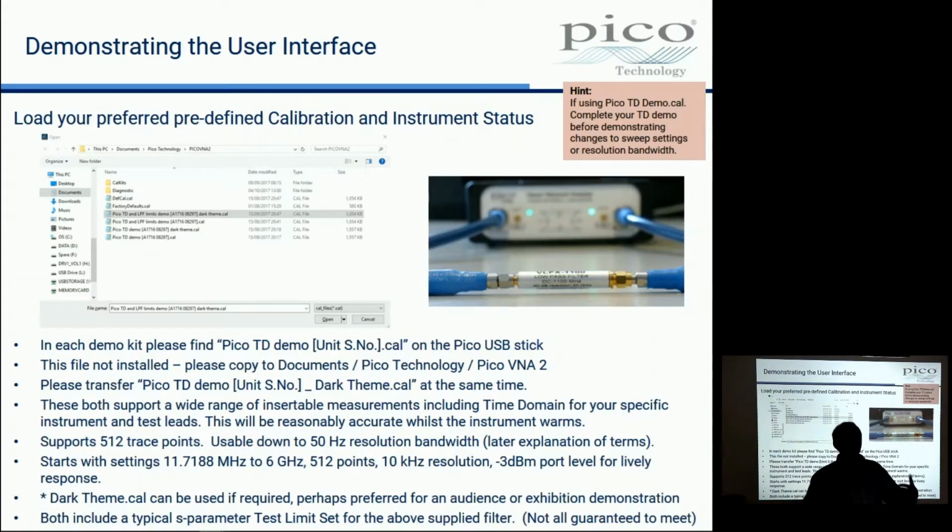But it's better not to, because it's a lengthy process and you want to be starting by talking about features and benefits rather than calibration. So we do as the customer asks, but in general they're going to want to see the thing operating first and foremost. You do not want to be doing a calibration, not least because you might feel under pressure to get it done fast, and that's the worst thing that can happen to a calibration.